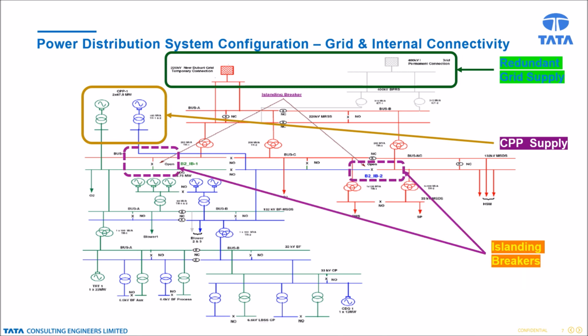In case of grid disturbance, grid system is isolated from the plant power system with tripping of both the breakers so that the total power failure to the plant critical loads can be avoided with availability of generator from captive power plant. It is desirable to deploy automatic load shedding system for a critical process plant with dynamic load shedding scheme. The operation of the dynamic load shedding scheme will restore balance between power supply and load demand within frequency stability limit of the in-plant generators. In the event of failure of the dynamic load shedding scheme, the under frequency based backup scheme can be deployed to shed sufficient load to arrest the fall in frequency to sustainable level.